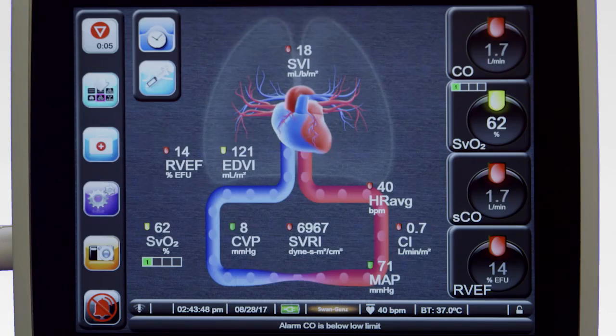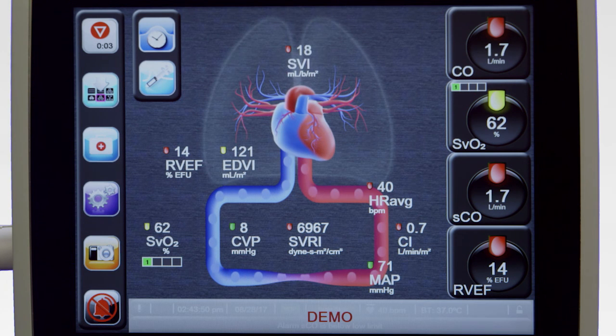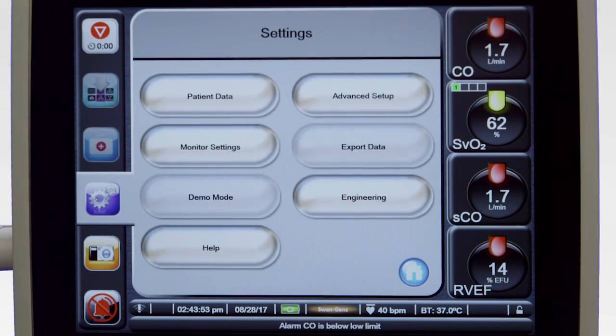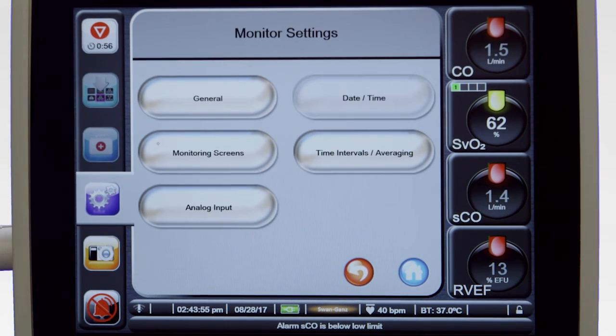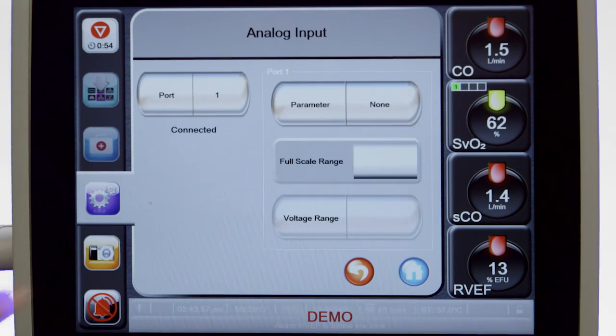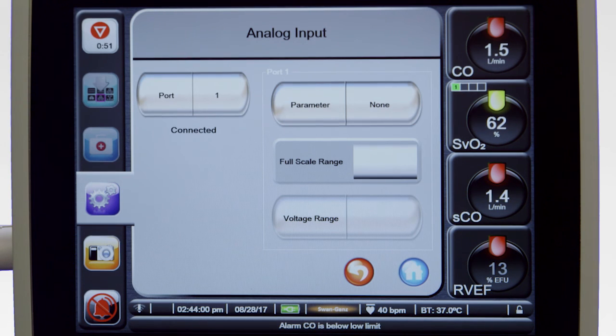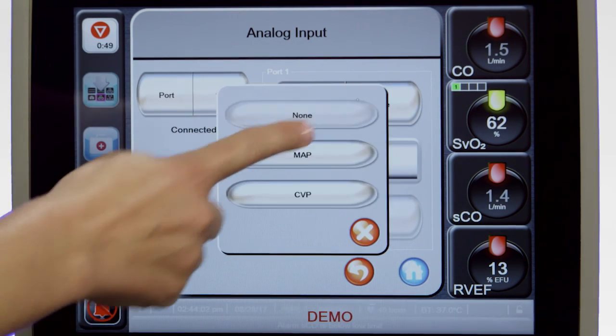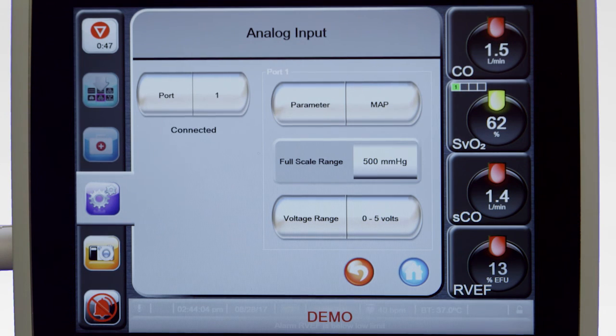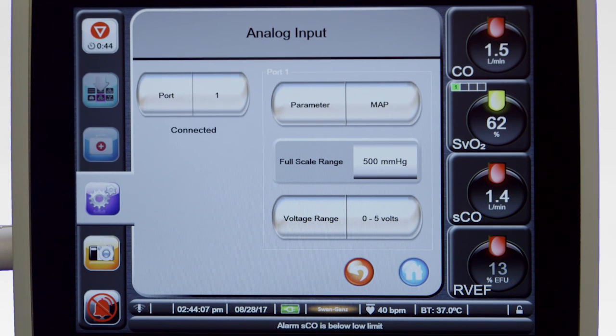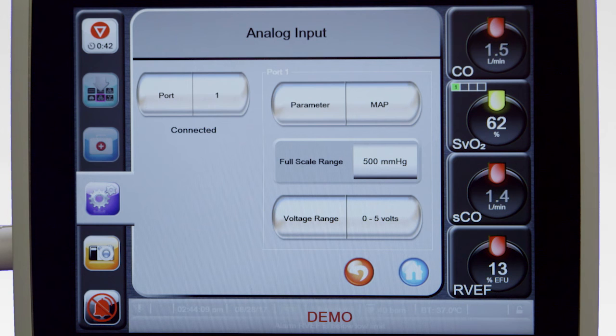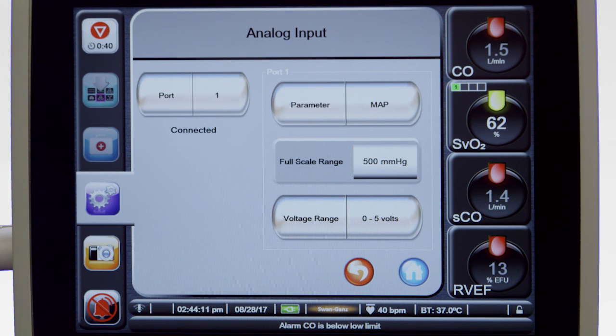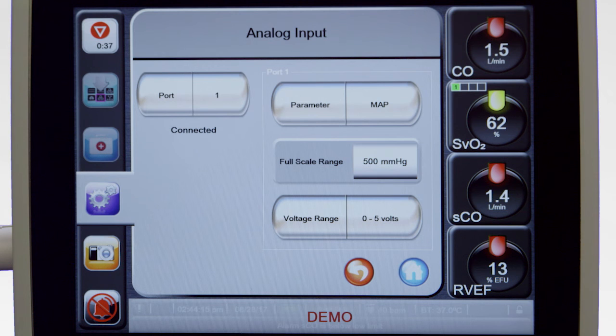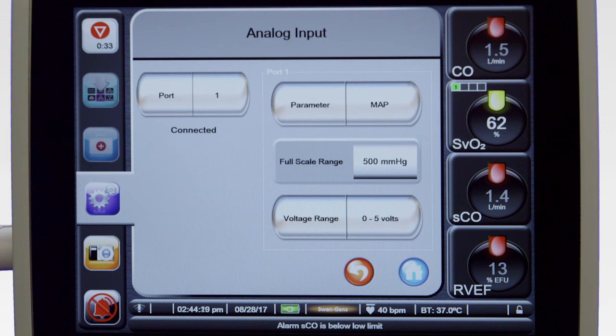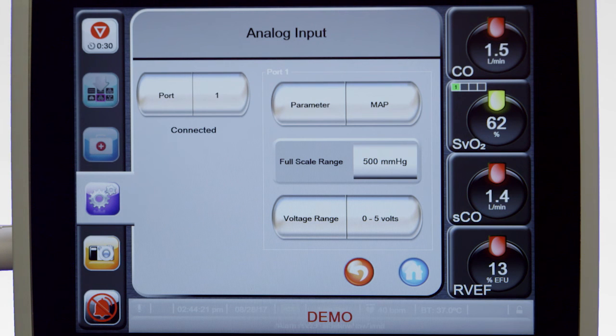To configure the HemoSphere Advanced Monitoring Platform for slave operation, touch the Settings icon in the menu bar, then select Monitor Settings and Analog Input. To set up analog port 1, select MAP from the parameter list. The default setting values for MAP will be displayed. If the default values are not correct for the bedside monitor being used, the user can modify the voltage range, full scale range, or perform the calibration option described in the HemoSphere Advanced Monitor Operator's Manual.